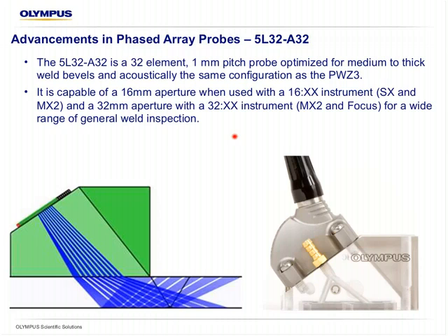The second of the probes in the new Weld series is the 5L32A32. Inside the housing are 32 elements of a 1 millimeter pitch, optimized for medium to thick weld bevels, and acoustically the same configuration as our PWZ3 with a much improved wedge design. So it is capable of a large aperture 16 millimeters when used with a 16 pulsar instrument, or a very large 32 millimeter aperture when used with a 32 pulsar instrument like the MX2 or the Focus, for a wide range of general weld inspection.